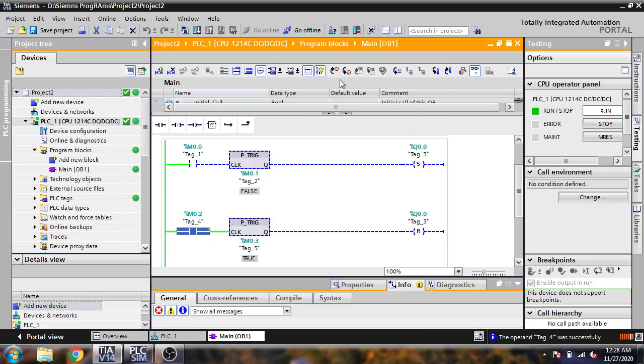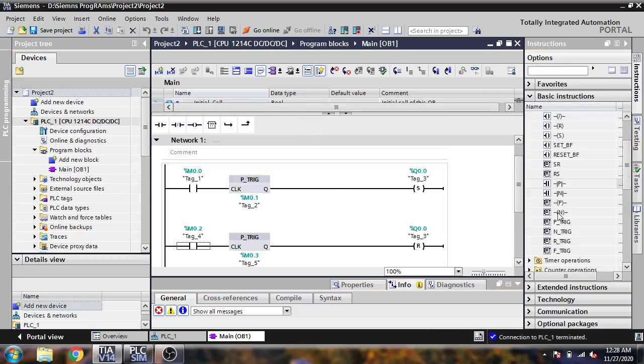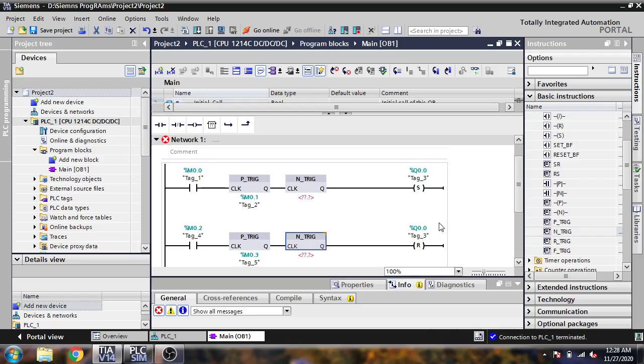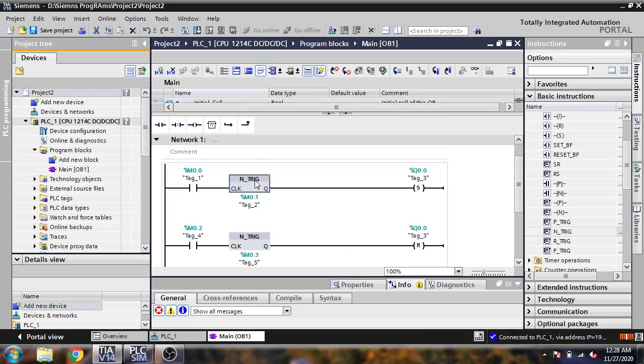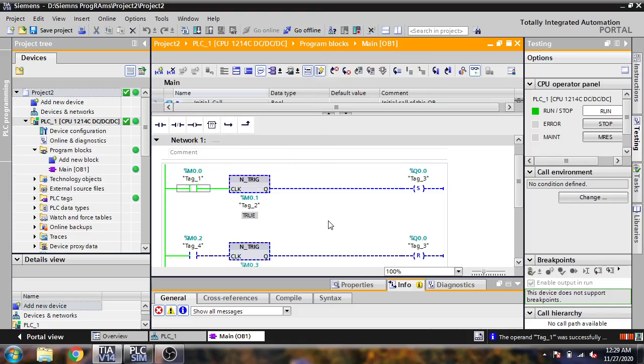Now I am going to change it to N_TRIG. I am just going to modify to 0. In N_TRIG you will see that after we go over the transition, it will set the bit. I am using M0.1 and output 0.3 there. After compiling and downloading to my PLC, you will see our output is not set when we turn it on — because when we turn it off, then our output will set. I go to 0 and you will see our output is set.